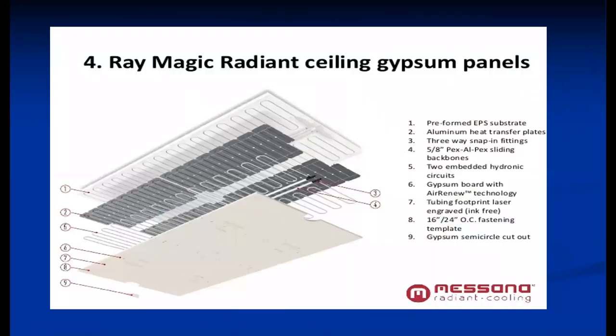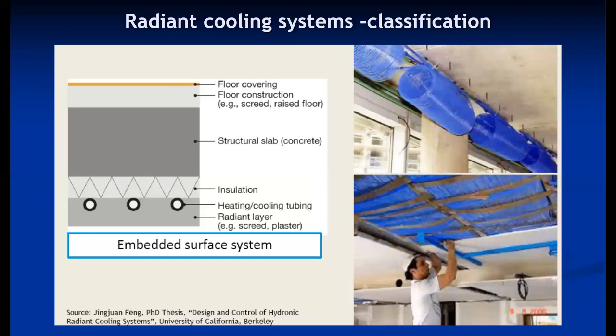There are different configurations and advances in panel design to enhance the rate of heat transfer and effectiveness of these surfaces. The third classification is the embedded surface system, where the original structure's surface is embedded. It consists of an insulation part, followed by heating and cooling flow tubes, followed by plaster. This technique can also be used for existing buildings. Except for the first type, both panel and embedded surface techniques are implementable in existing buildings.